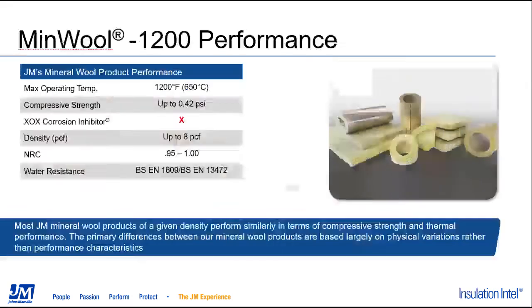So some highlights again, rated to 1200 degrees Fahrenheit, compressive strength of a little under 1 pound per square inch, does not contain the XOX corrosion inhibitor. The most common density is 8 pounds per cubic foot, though for some of the configurations we do offer other densities. In addition to the ISO 15665 classification and testing for acoustics, there's also a noise reduction coefficient or NRC rating for our mineral wool products that is an additional indicator of acoustic performance. So that would be something else you can look at in that area.